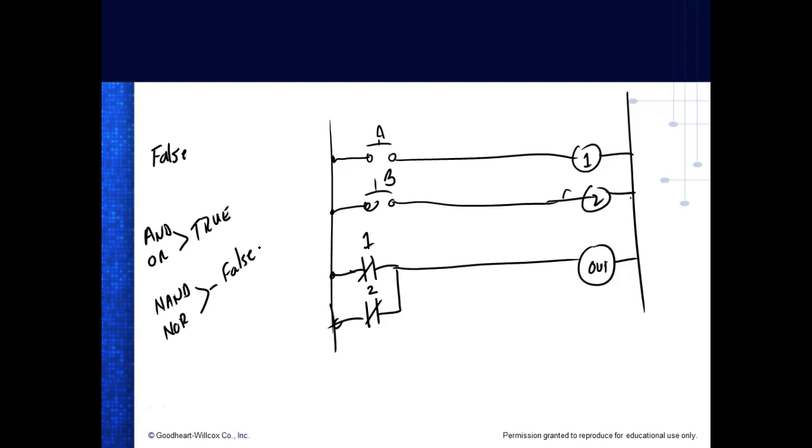So what we do for ANDs and what we do for NANDs is we normally use examine if open. Now, this isn't a stop circuit. This is logic. So for all my logic inputs, I would use a normally open push button on my PLC, every one of them. So we're using examine open, right? I have to press both of them. When I press them, they go false, right? Make sense? So relay normally closed contacts, examine open contacts in parallel, makes what we call a NAND.